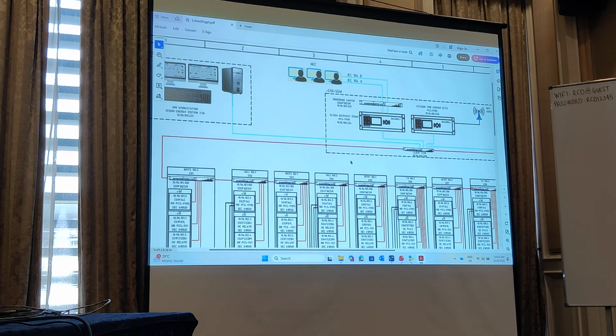So each 61850 has its own function. But what I said was that the functionality of receiving and transmitting, you can record as well. But the problem with that functionality is they don't have a timestamp. They don't have a quality, not timestamp. Time quality is not there. So that is the reason it's not being monitored. But as I said, you can monitor using a sniffer and all those kinds of things.